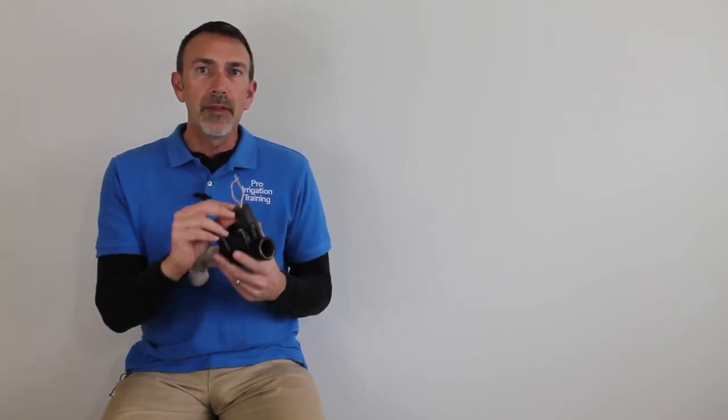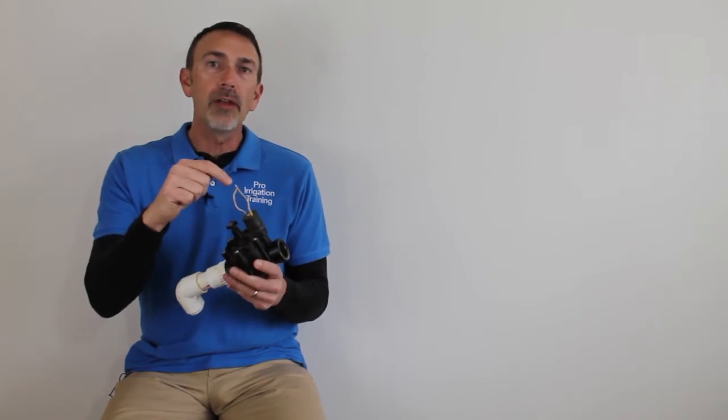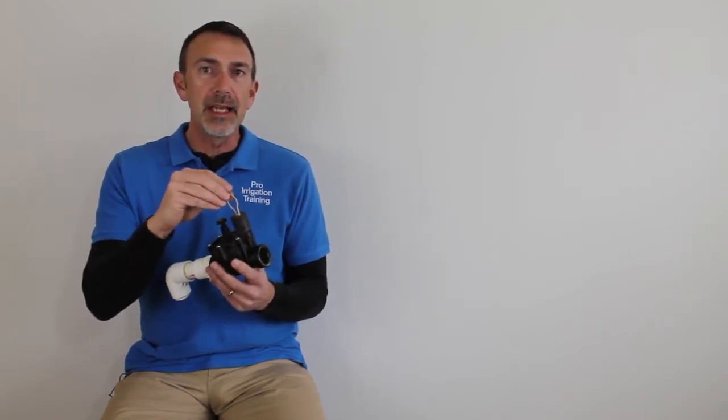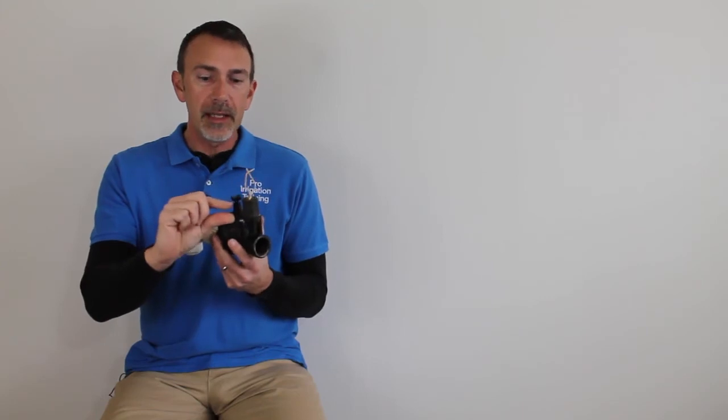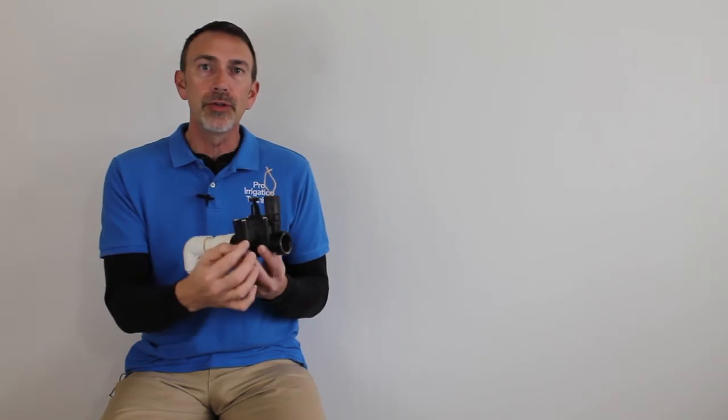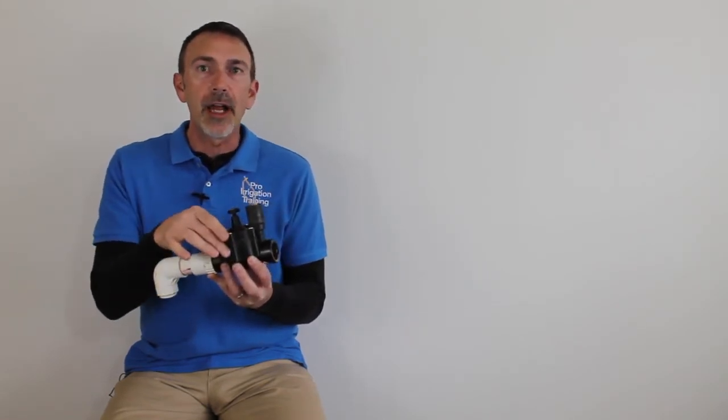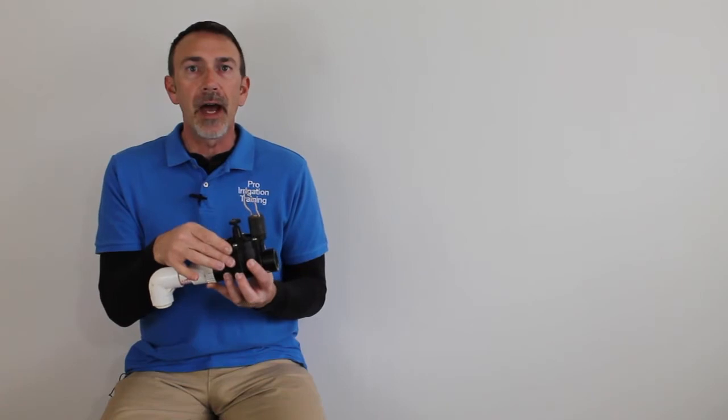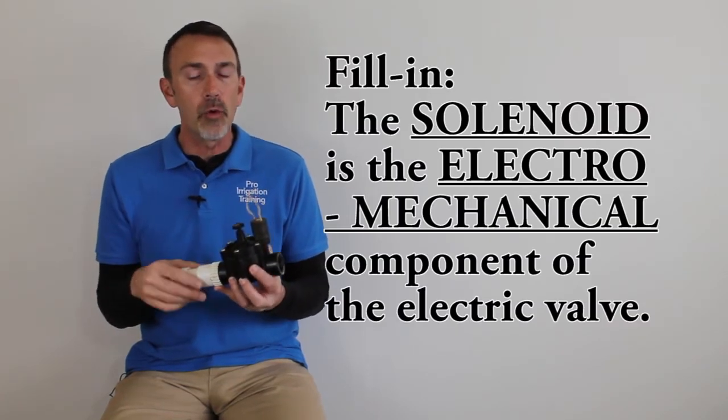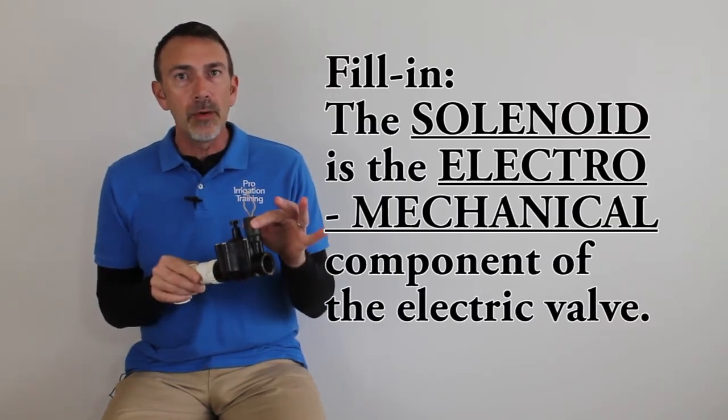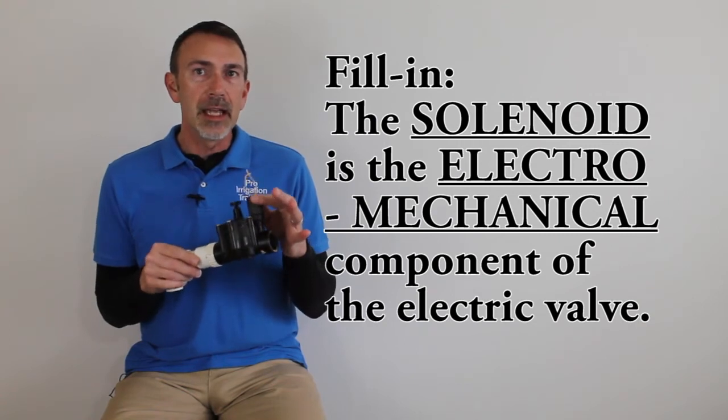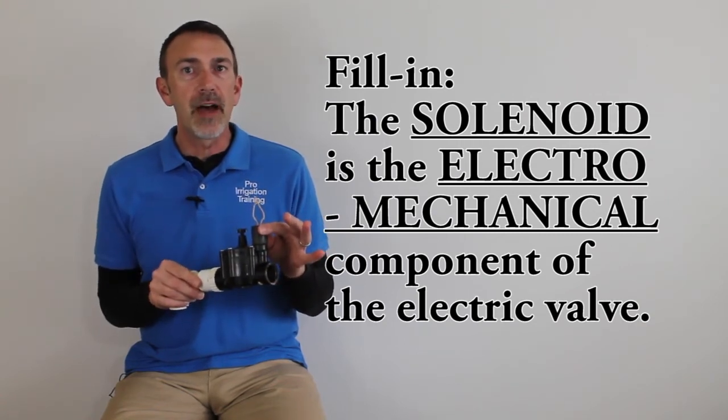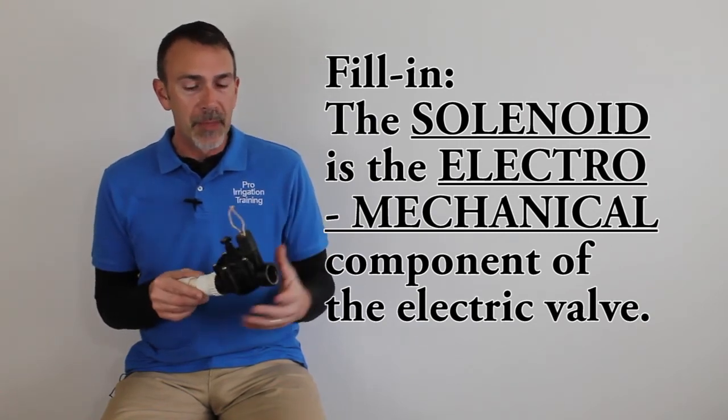So what happens inside of this solenoid, there is a little metal plunger that has a coil of wire around it, and when electricity is applied to the solenoid, it works as an electromagnet and it retracts the plunger and allows water to move through the series of diaphragms and openings inside the valve. We will talk about that later in our valve course, but for now all you need to know is the solenoid is the electromechanical portion of this valve that causes it to operate.